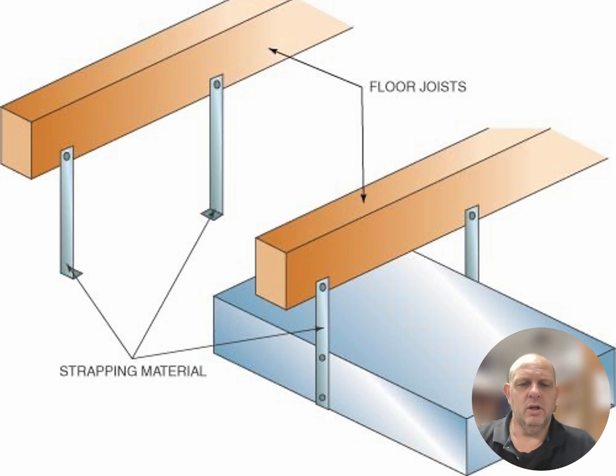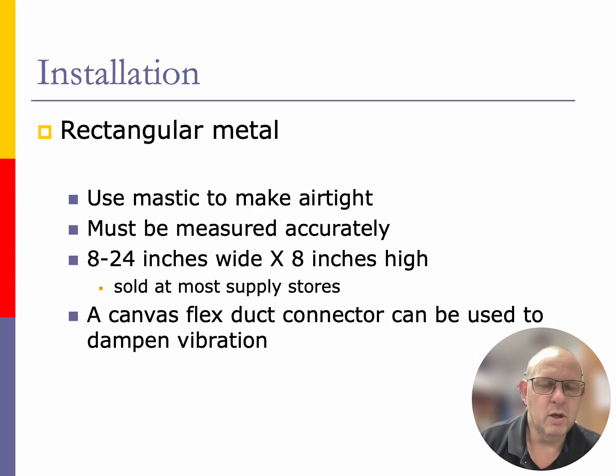Another thing that we're going to have to worry about for our metal ductwork is the sealing of that duct. Now I'm talking about the gaps that come together where our drive cleats are and where our S-lock is. That air will leak out of there. Also the Pittsburgh, which is the joining of the two pieces of metal together to make our square duct, will also leak, and we want to put mastic on that as well. And mastic, all you can think about is mastic as caulk on a brush. That's what mastic is. So when we talk about the actual ductwork on our system, we're referring to rectangular duct.